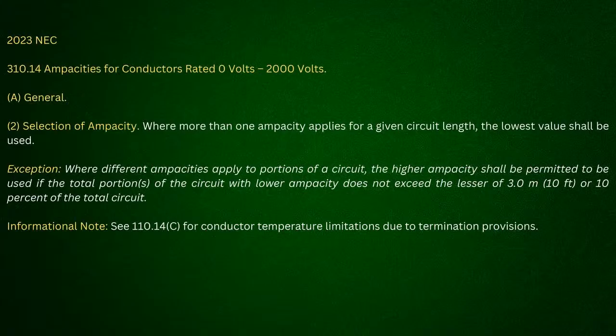Yeah, and it's not that I'm arguing with you. I'm just saying, anybody that argues it, oh yeah, I do agree with that 10 foot or 10% rule. I think that's actually good, but just to explain, it seems like I explain the same thing a lot. Let's just say you bundle the crap out of it, you go 60% on a nipple up to a gutter wireway, and then you go 100 foot out there. What the code says is that short section is less than 10 foot of the overall run, so that's going to act as a heat sink and reduce the heat. So it might be a little bit hot in that nipple area, but for the length of the run that heat's going to dissipate, and that's actually code compliant.